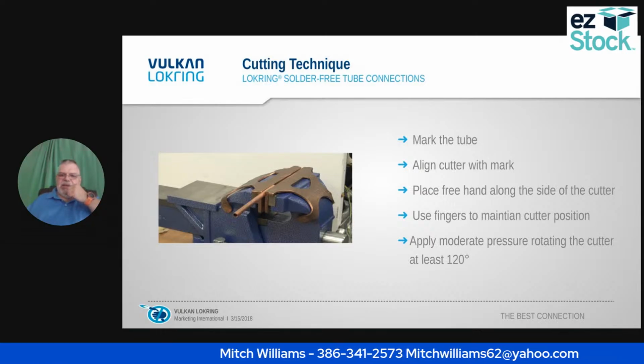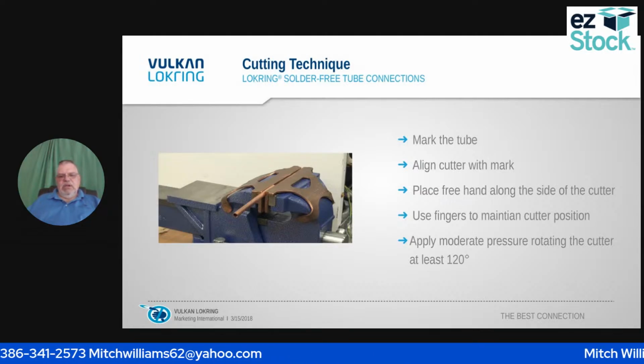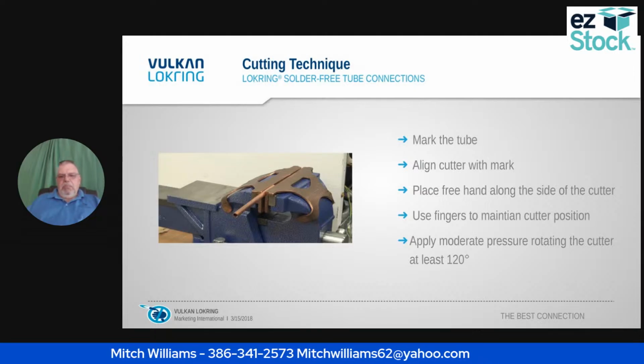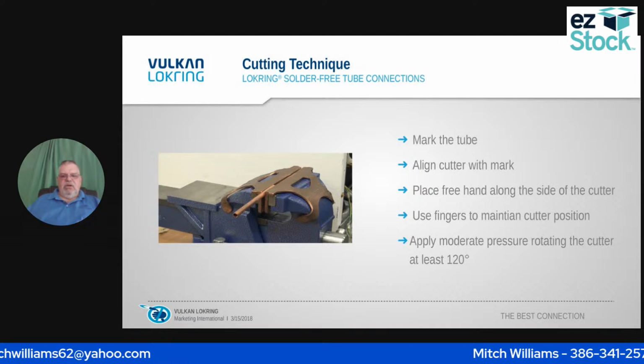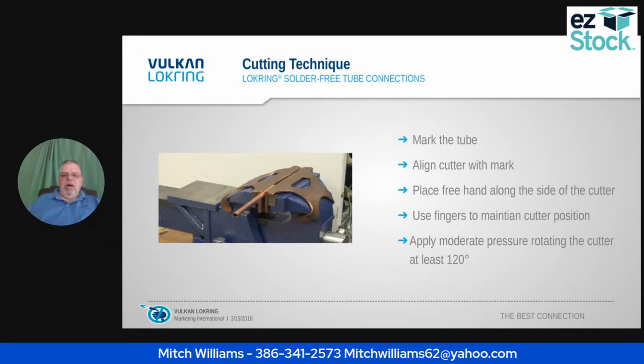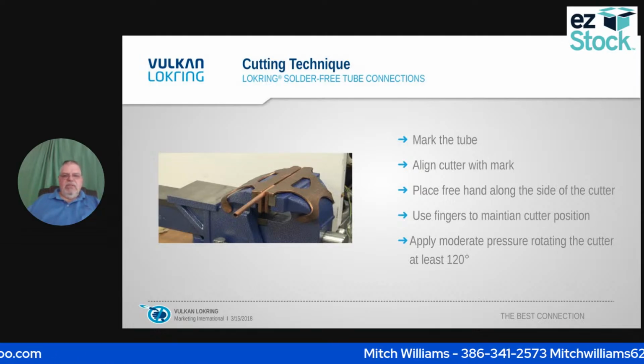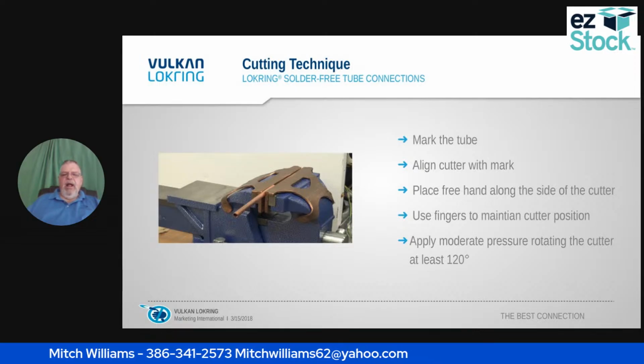So how do I do this? I'm just going to mark the tube that I need. Granted, this is a vise. This is not a real world thing, but this is the way that you would use it in any instance. I'm going to line the tubing cutter to my mark. Then I'm going to place my free hand along the side of the cutter. I'm going to use my fingers to maintain the cutter position, and I'm going to apply a moderate pressure, rotating the cutter at least 120 degrees. If I can get all the way around, go ahead and get all the way around. But the nice thing about these pliers is I can do it all from a 120 degree range.